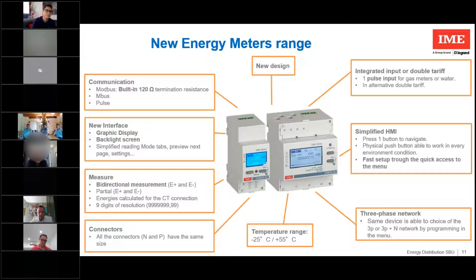Going even more specifically, here we see a focus of the new graphical display, capable of displaying powers and energy on the 4 quadrants. We also added the voltage and current phase angle. That is an important value to find, for example, a bad insertion. So if you have more than 120 degrees of angle distortion, you have a bad insertion of the voltages.